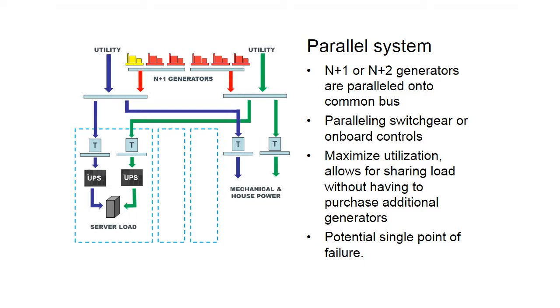One of the negatives to a parallel system is basically that the generator bus, that parallel bus, becomes a single point of failure. So recently what we've seen is we've been trying to split that bus into two. On a data center we did recently, we were able to, because data centers use a lot of free cooling a lot of times during the year, they don't need as much load. The load is a little bit lower. We were able to split that into basically a 2N system, and then that 1 month a year when we have peak heating and peak cooling, we close the tie and we use an N+1 system. So it's just a way to help protect against that single point of failure.